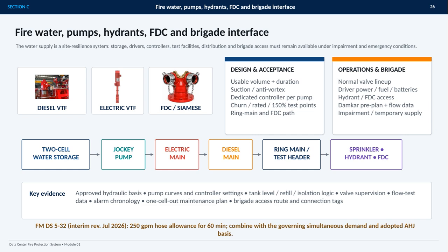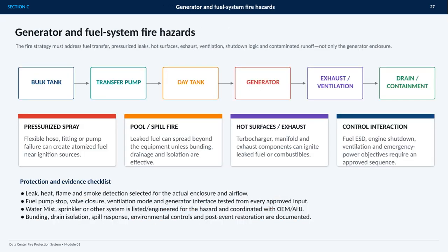demand and AHJ basis. This section focuses on generator and fuel system fire hazards. The key point is that the fire strategy must cover the entire fuel and equipment pathway, not just the generator enclosure. Fuel moves from the bulk tank through the transfer pump to the day tank and generator, creating several opportunities for loss of containment. Pressurized spray is especially hazardous because a failed hose, fitting, or pump can atomize fuel near an ignition source. A pool or spill fire presents a different challenge.